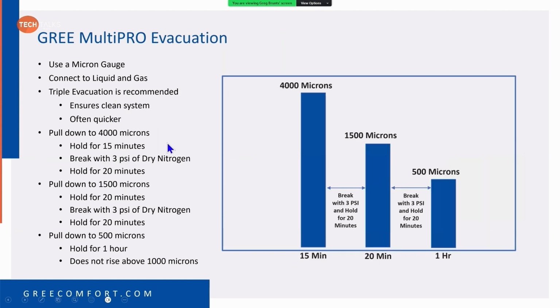And then, there's a lot of piping with MultiPRO, so we recommend that you do a triple evacuation. We give you a recommendation to pull it down to at least 4,000 microns, hold for 15 minutes, break it with 3 pounds of nitrogen, hold for 20 minutes, pull down to 1,500 microns, hold for 20 minutes, break with nitrogen, hold for 20 minutes, pull down to 500 microns, hold for an hour. Does not rise above 1,000 microns.